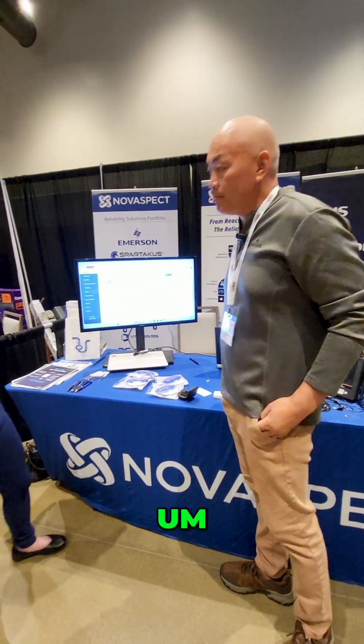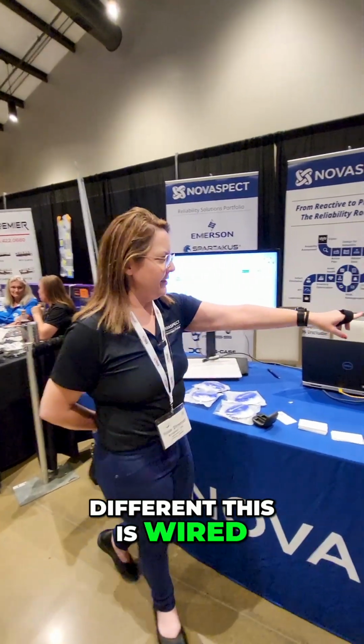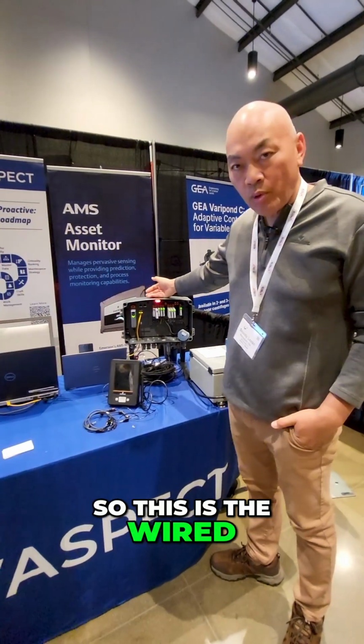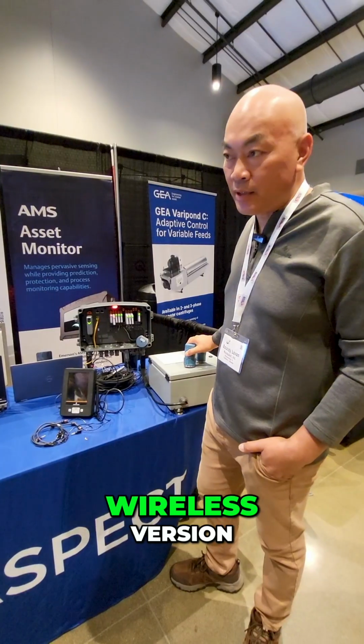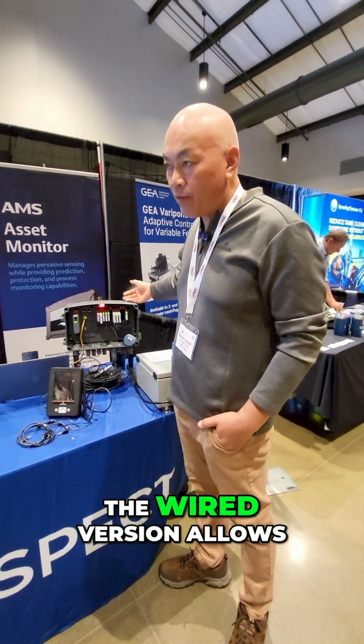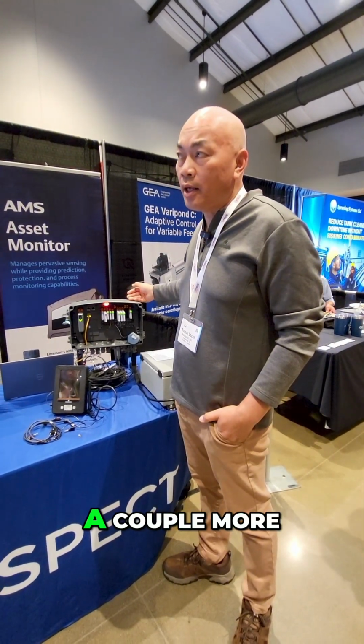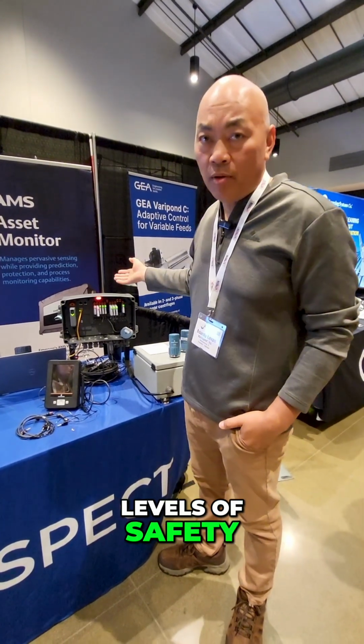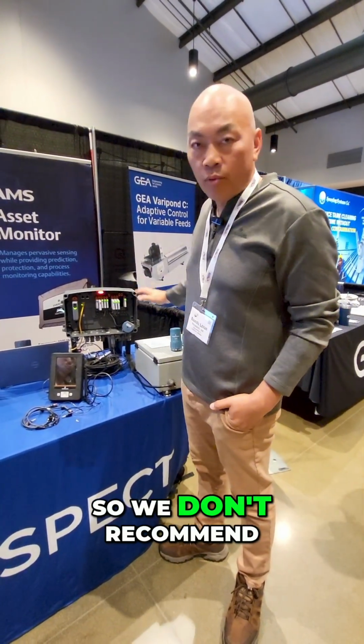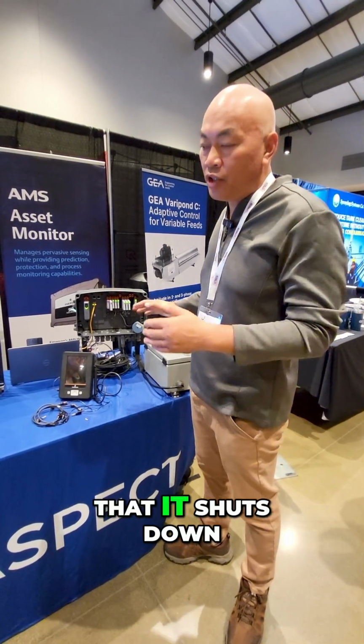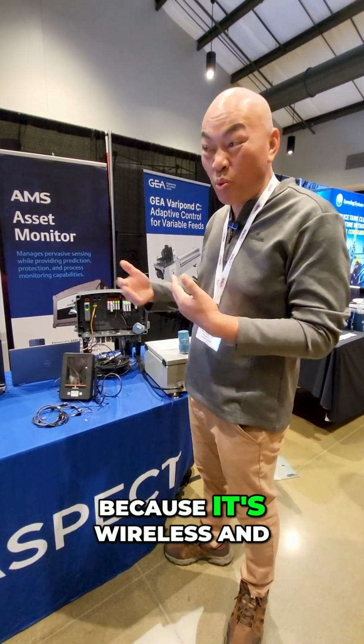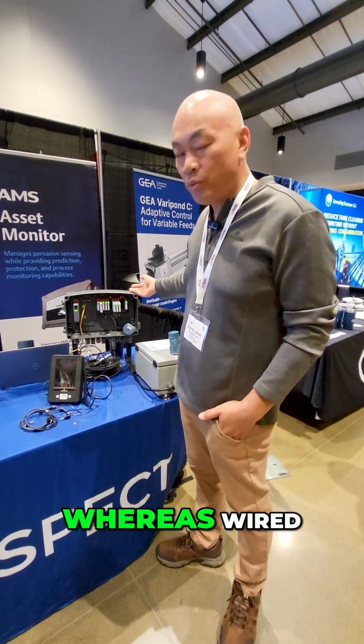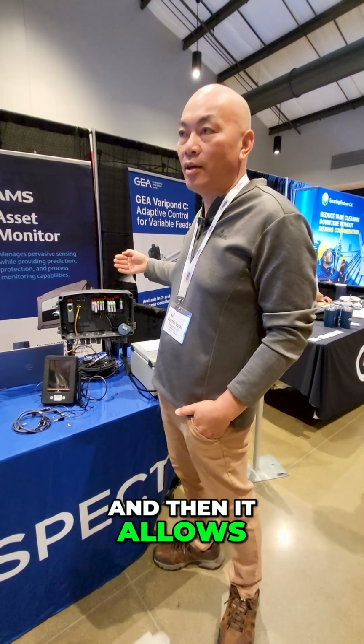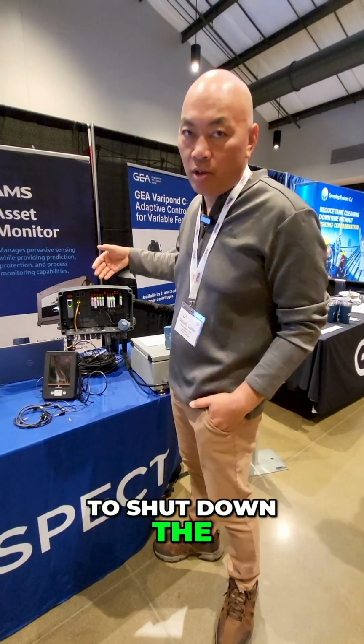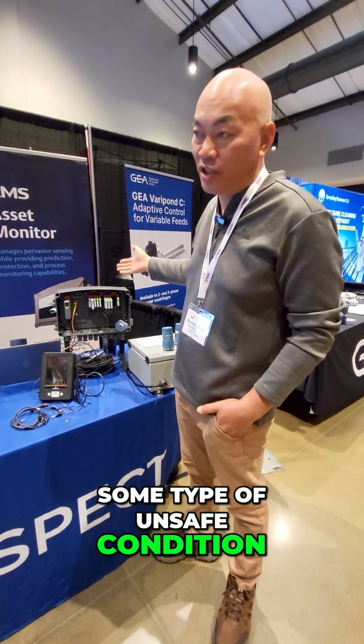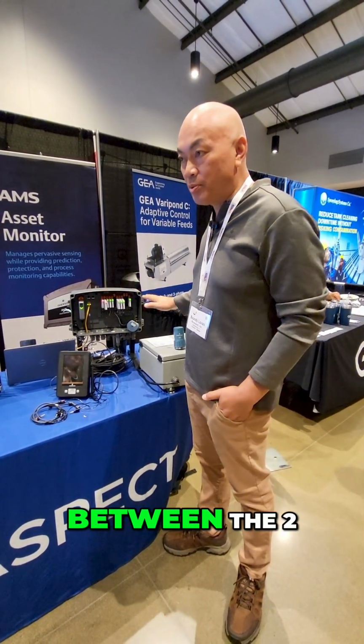Cool. So this is wired, and what are these? This is the wired version, and this is the wireless version. The big difference is the wired version allows you a couple more levels of safety, whereas the wireless doesn't. We don't recommend that wireless shut down the equipment because it's not continuously monitoring. Wired is continuously monitoring, which gives you a higher level of confidence to shut down the equipment if it's at some type of unsafe condition. That's the big difference between the two.